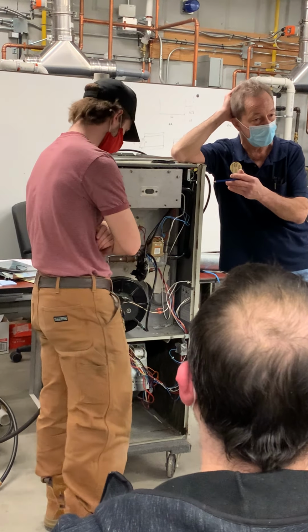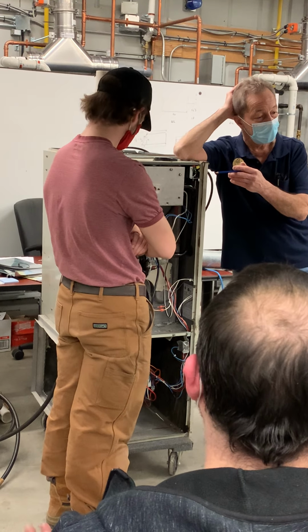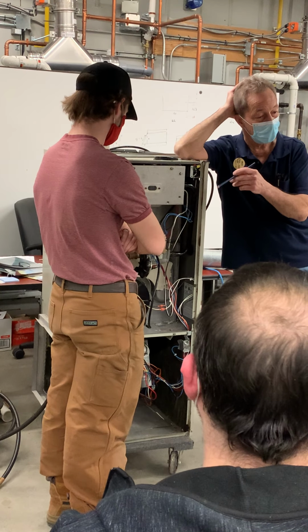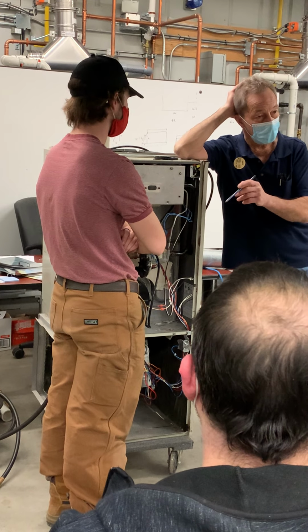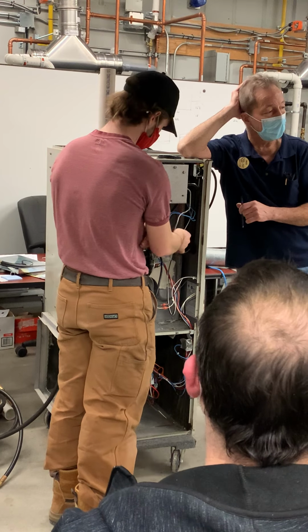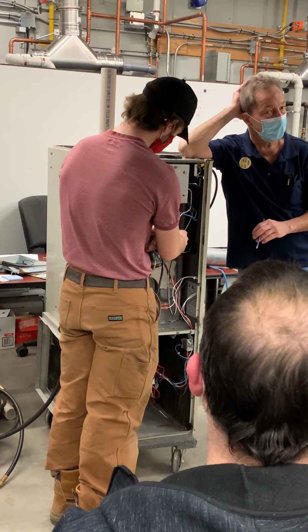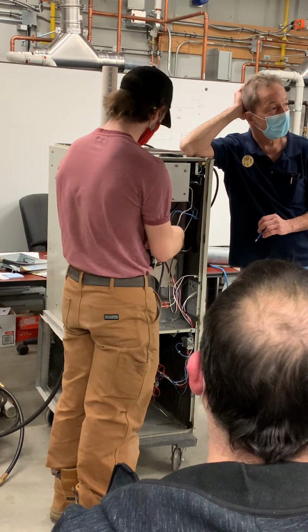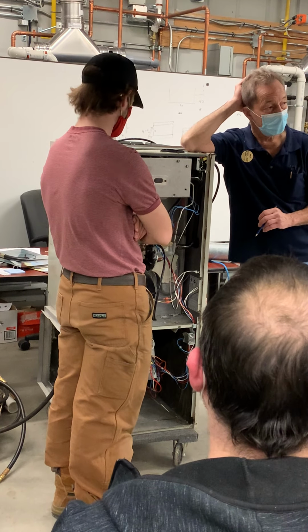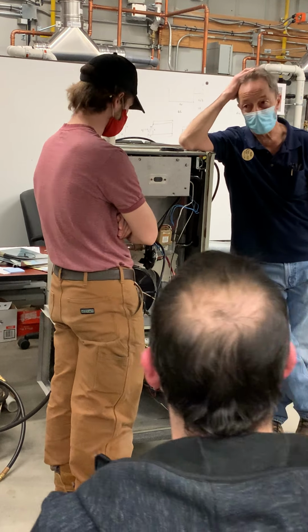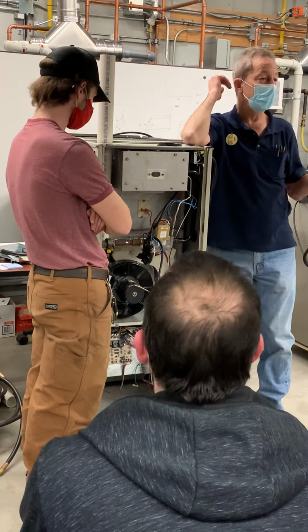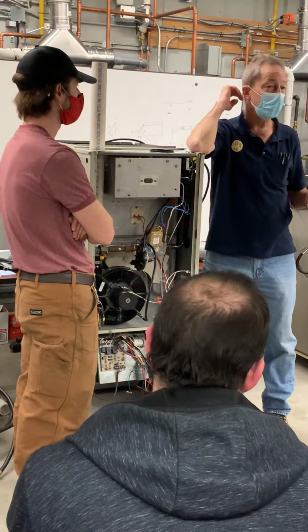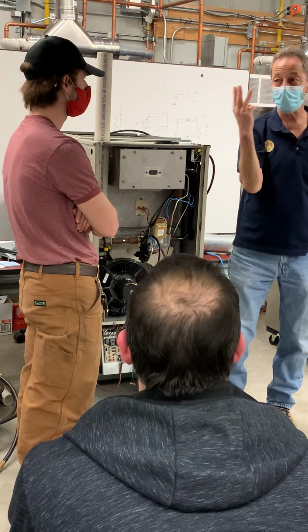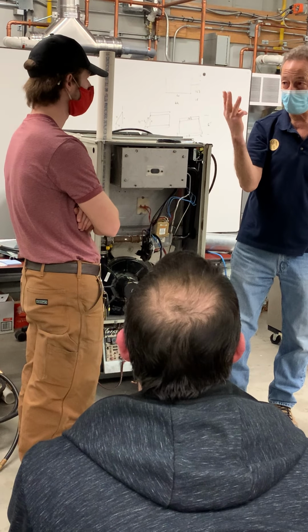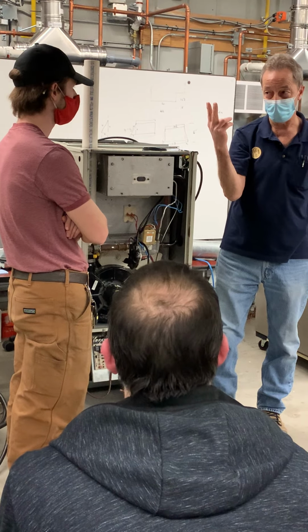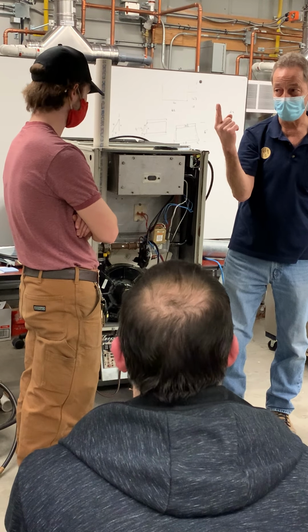What voltage is the gas valve? 24. What voltage is the HSI? 24. Do you see another black wire going into the burner area? Yep. What do you think that's for? Probably like a flame sensor. Thank you. So you got 2 blue, first off, you know it's a Honeywell smart valve, so you know you got a pilot. And you know that you've got an HSI and a flame sensor. You got 3 wires going into the burner area. If it's spark ignition, you'd only need max 2. Maybe more. If it's integral, you'd only need 1.